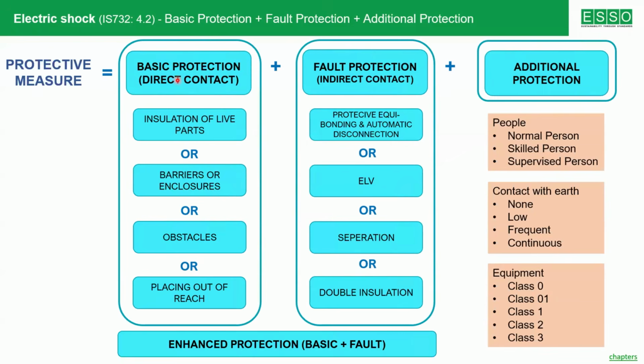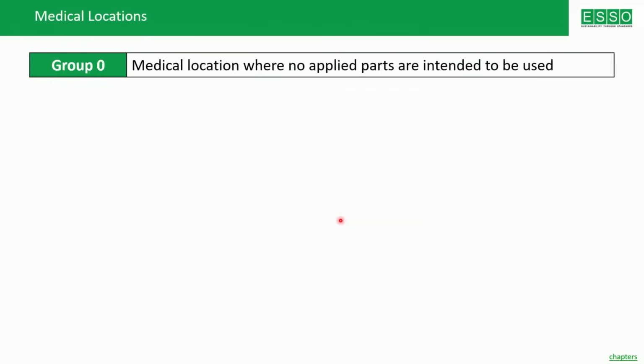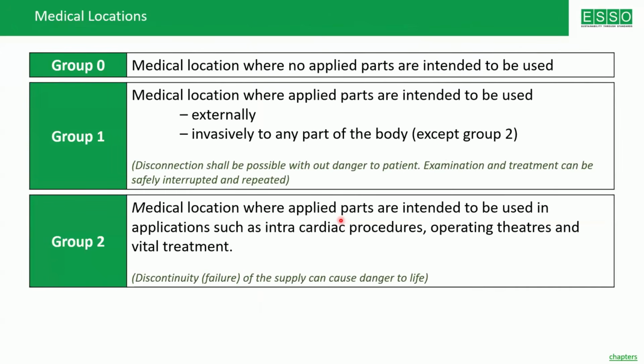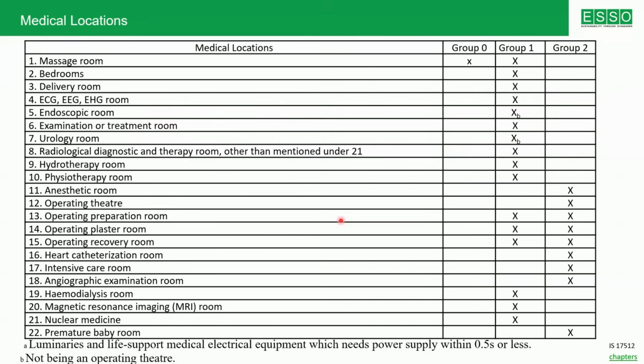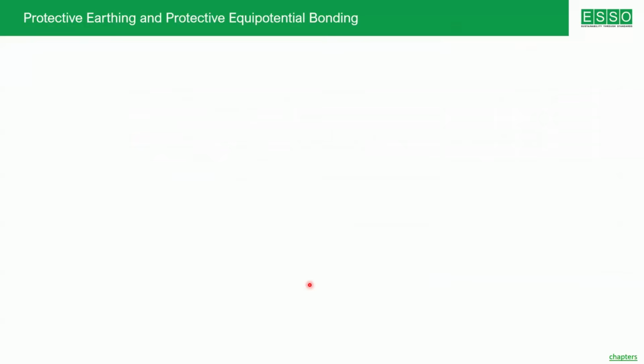Protection against electric shock is achieved by basic protection, fault protection, and additional protection. We have explained this in multiple webinars, so please go through the old webinars. You will be able to understand the protective measures required for basic and fault protection. Medical locations need additional safety measures. That is very, very important. For that, what do we do? The medical locations are classified into group 0, group 1, and group 2 locations. I explained about this in the last webinar. Now, the classifications are very much included in the standard.